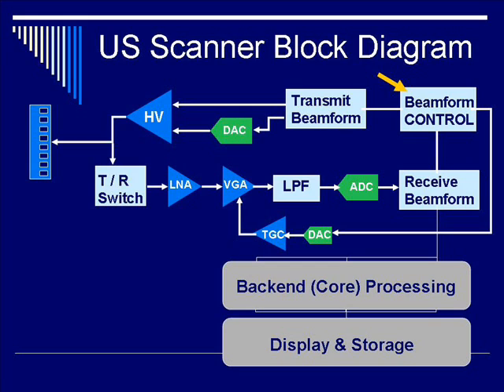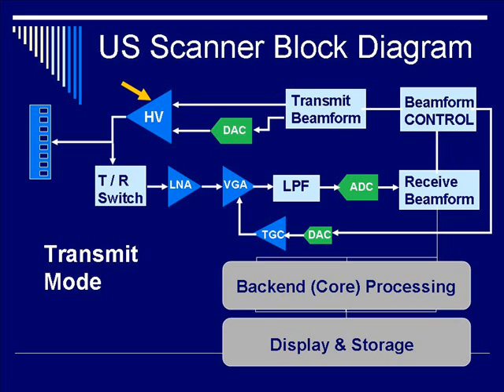In terms of how the chain of events happens within transmission, the beamformer control is the brains behind beam shaping of the transmission pulse. During transmit mode, it delivers a set of digitizing sequences to the transmit beamformer, which in turn gives off a sequence of pulses that, in conjunction with the DAC (digital-to-analog converter), drives the high-voltage pulser. The high-voltage pulser yields an output signal that drives the transducer itself. Due to the piezoelectric effect, this electrical signal is converted into an acoustic signal.